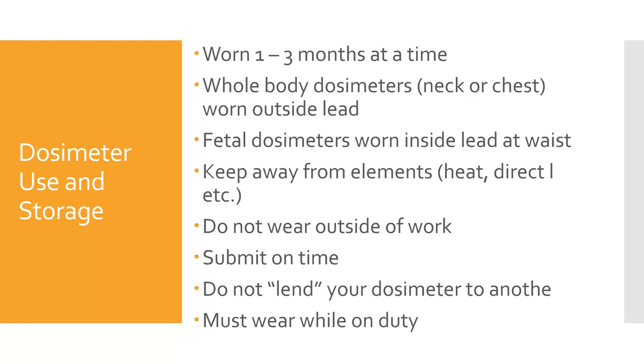Be sure to keep your dosimeter away from heat, and be mindful about where you store it. Whenever possible, store it at the facility where you are working. Do not store it in your car where extreme temperatures can interfere with the reading. Do not take your device on airplanes or wear it during your own medical imaging procedures. Make sure to keep track of your device — one that is not worn or not submitted does you no good. In some states, the technologist can be held accountable for not properly wearing and submitting their personal dosimeter. Make sure you are the only one wearing your dosimeter and that you wear it while working, so your radiation dose, tracked throughout your career as a radiation worker, is accurate.